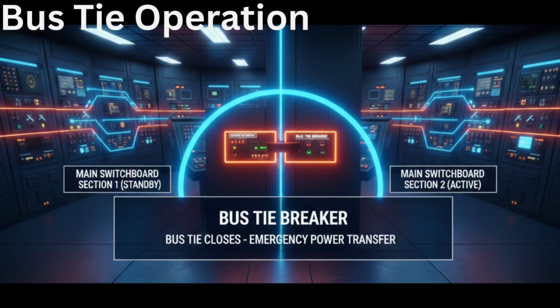Bus tie operation. Many ships divide the main switchboard into two sections for reliability. These two sections are connected through a bus tie breaker. During normal operation, both sections may operate independently. If one section fails due to fault or maintenance, the bus tie breaker can be closed to supply power from the healthy section. This ensures continuity of power and reduces blackout risk.